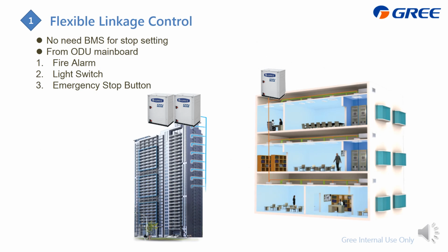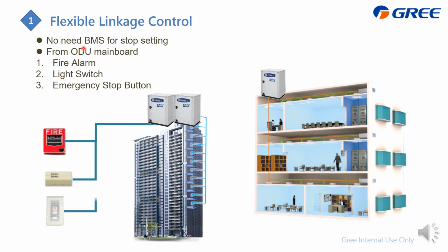And the same as the air cool, we don't need a BMS for the stop setting of the outdoor unit. You can just connect the fire alarm switch or the emergency stop to the outdoor unit, then it can stop immediately. So for example, in this case, in this building, they just installed a water cool, and if we find that there is a fire here, this fire alarm will send the signal to the outdoor unit, then it can turn off the whole system immediately.